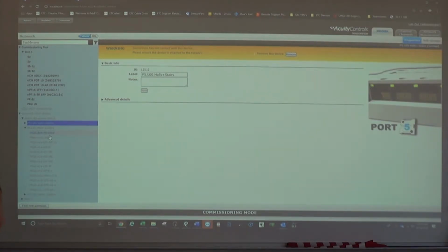Optosplitters. DMX uses similar things. I forget what they're called in the fire alarm world because I'm not that dude. But basically, each one of these ports breaks the copper connection and translates it into a digital light, then goes to the next port, transmits into a digital light back into copper. So each local zone is one straight line of copper. And in order to get around the splitting or the wiring, each one of these is optically isolated, so we're breaking the copper connection and starting a new one each time.